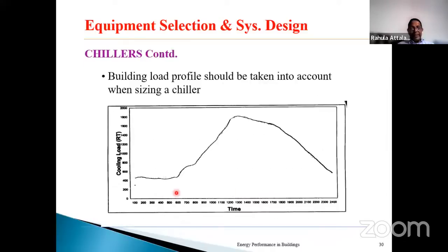All these decisions have to be taken by proper understanding of the cooling load of the building. Cooling load is something that can be measured or can be obtained by simulation. You see the early morning load, and it goes up. Depending on the load requirement, we can decide on the number of chillers. So here you can have a smaller chiller, then an additional one, and at the top another, depending on your end use requirement. You can also put one single chiller to cover everything, but then that chiller will be at very low load condition where efficiency will be quite poor. So equipment selection and the number of chillers would entirely depend on the cooling load profile, which has to be properly estimated.